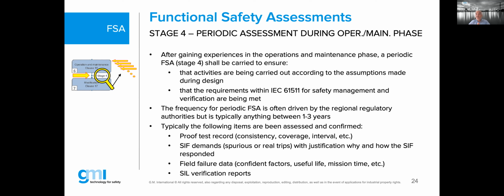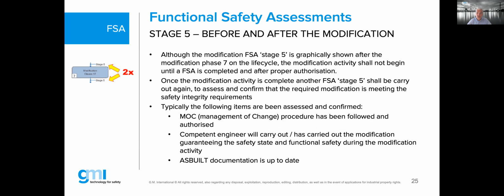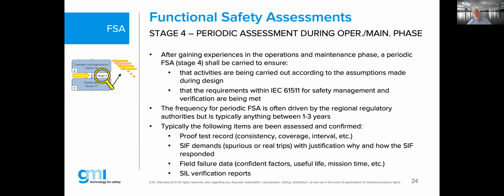In different countries where I'm traveling around the world, it varies between 18 months and the longest one I heard was 5 years. So again, it depends on the regulatory bodies, or sometimes it also depends on large corporate offices or companies who have different sites around the world where they have their own internal culture, where they will say how frequently they have to carry this out. Frequency, as I mentioned, can be anything between 1 to 3 years, maybe 5 years, but the more current ones we see and experience are between 1 to 3 years.